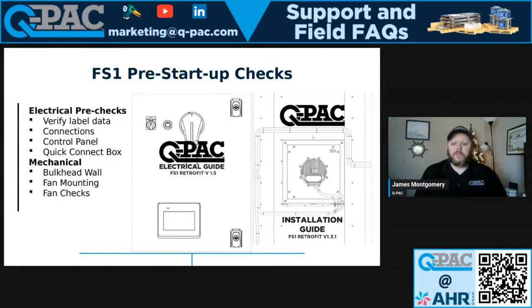Moving on, the control panel itself has a fused inlet or a fused disconnect. That's where your high voltage is going to come directly from your distribution network or your distribution system, whether that be a panel or a transformer directly, however you've got this wired. Obviously, your local NEC electrical codes are going to come into play here. That inlet connection is a pretty large connection. You're going to make sure that thing is tightened down.